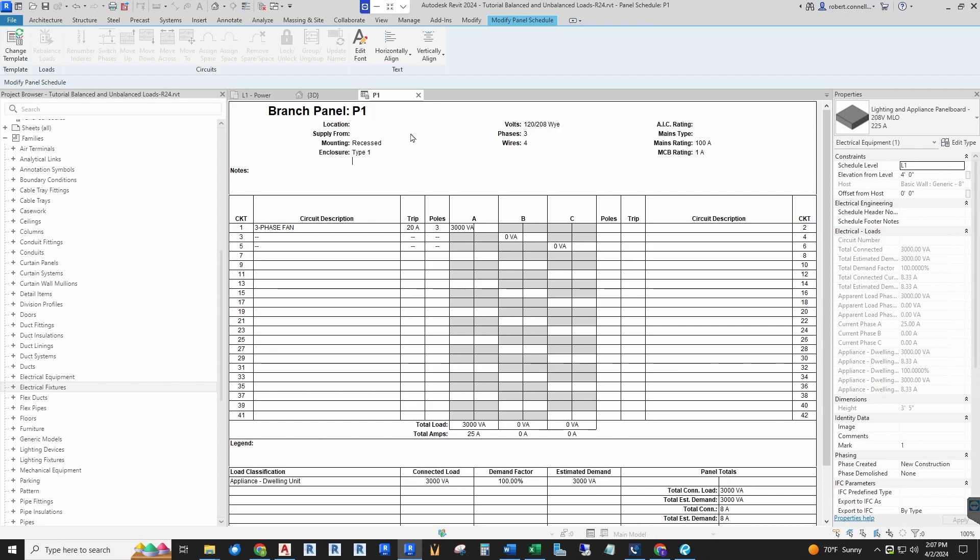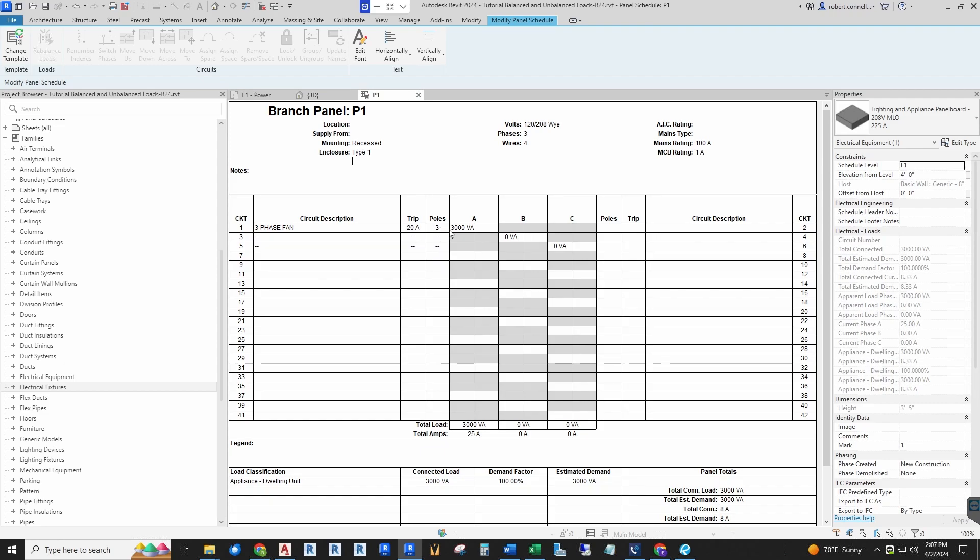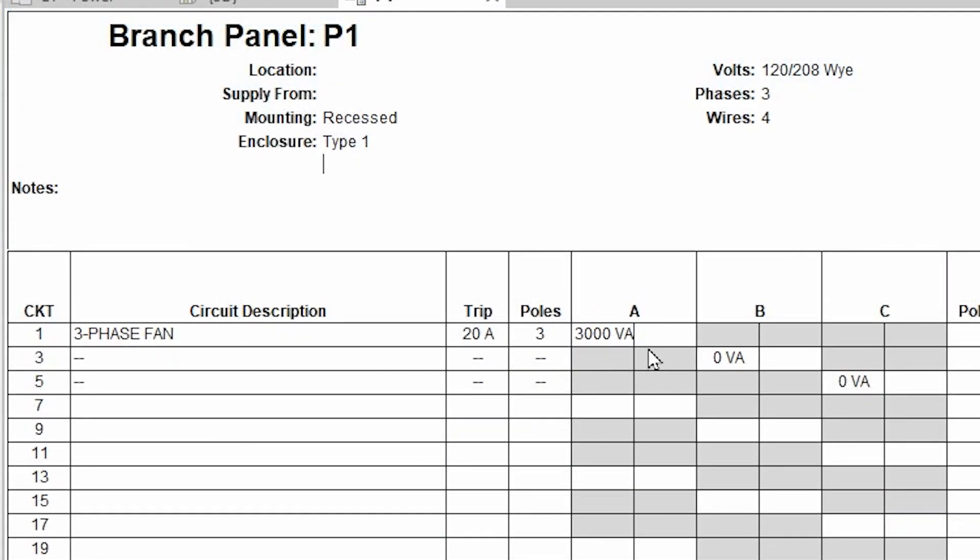For example, what we have is a branch panel P1. In the circuit description you can see we have a three-phase fan, and it is indeed taking up three poles of this panel—20 amp trip, three pole—but the load only shows up on phase A. The full 3kW has not divided appropriately to the other phases. So we're going to tackle this issue and hopefully you will learn how to deal with this for your projects.